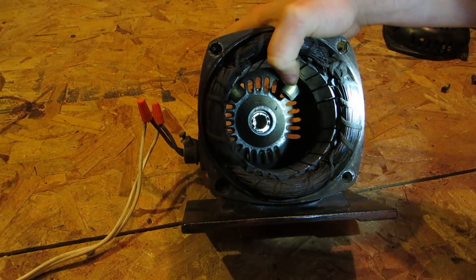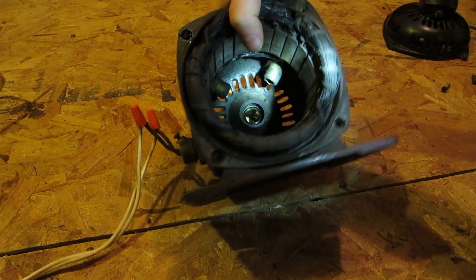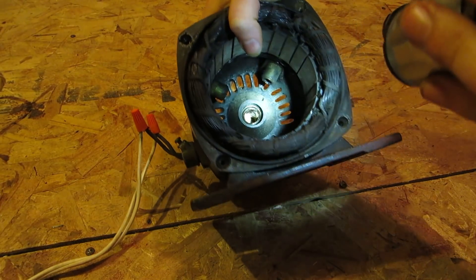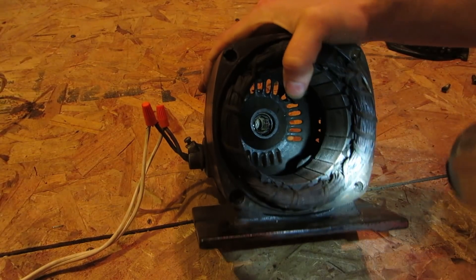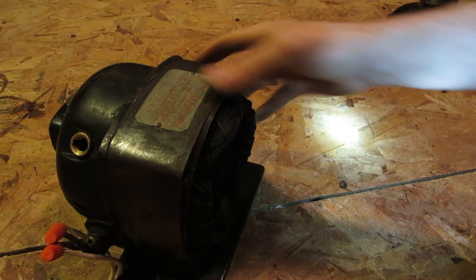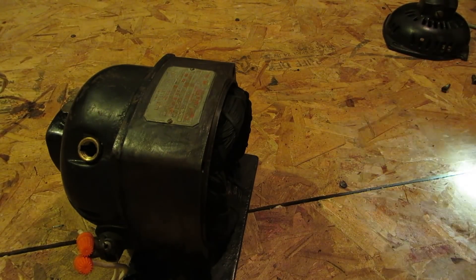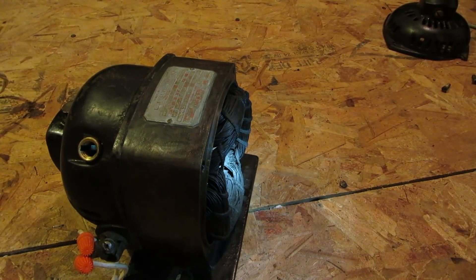You've got your stator — looks like a four-pole stator, similar to smaller synchronous motors. There's where your brushes come in, so they're at a 45-degree angle to each other. The ones that have the brushes actually pull away from the armature and disengage — they're a little more complicated. They've got a clutch assembly that moves them away and all that.